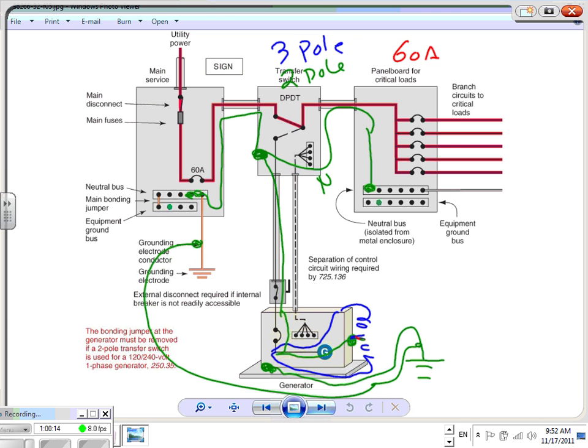Okay, now, if you have a transfer switch, can you guys see the transfer switch? It takes an act of God and somebody determined to kill himself to connect the generator to the grid at the same time, because the auto transfer switch, guys, is double pole, double throw. If it goes to the utility side, it is connected to the utility. When you move it to the generator, it switches first from the utility and goes down to the generator on every pole, and the neutral if it's a separately derived system. So why don't I have to have a tie between the circuit breakers? Because the transfer switch will act as a separation between the grid, the utility, and my separately derived system or non-separately derived system, the generator.